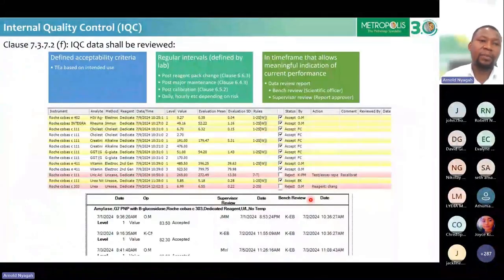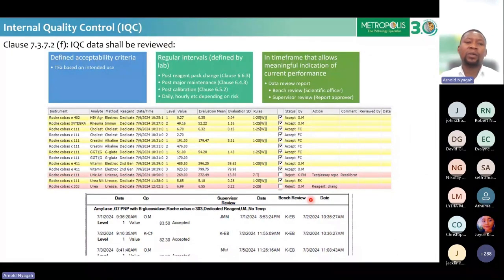So that when it flags that there is an outlier, you need to take the necessary action. Then the requirements also tell us that IQC shall be reviewed within a defined acceptability criteria, at regular intervals, and in a time frame that allows meaningful indication of current performance. So in our case, how have we been able to demonstrate to our assessors that we fulfill this clause? For defined acceptability criteria, there are total allowable error and other guidelines that are available, whereby we map depending on the intended use of these tests.